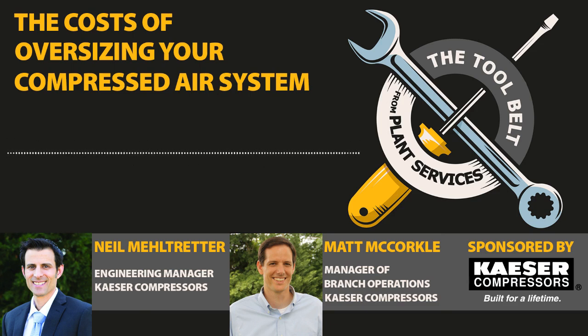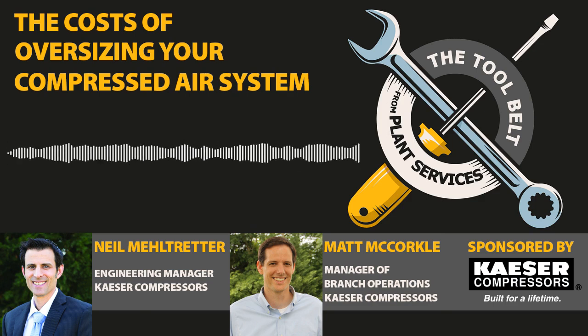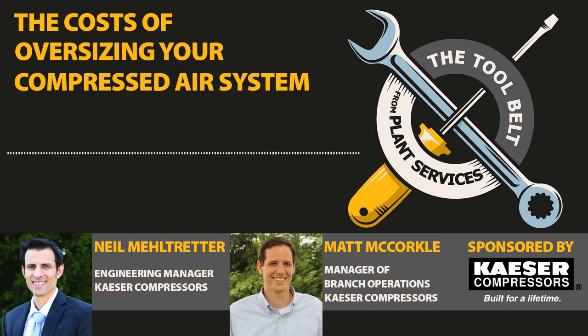What we like to say is anything really above 25 kilowatts per 100 CFM, that's where you start to lose your efficiency. If you look at a CAGI sheet for a brand new compressor, depending on what operating pressure you're at, you could be at 19 kilowatts per 100 CFM, 17, and some two-stage machines maybe 16. And if it's at 95 PSI, it might be even better. So there are some significant efficiency gains there. Again, specific power is a really good indicator.